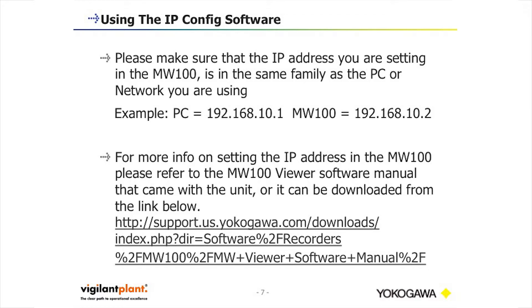Please make sure that the IP address you are setting in the MW100 is in the same family as the PC or network you are using. For example, if your PC is 192.168.10.1, the MW needs to be at least one digit different on the last octet, but the same for the first three octets. Octet 192, octet 168, and octet 10 should be the same on both devices. The last digit is your address representation — for example, PC is .1 and MW100 is .2.